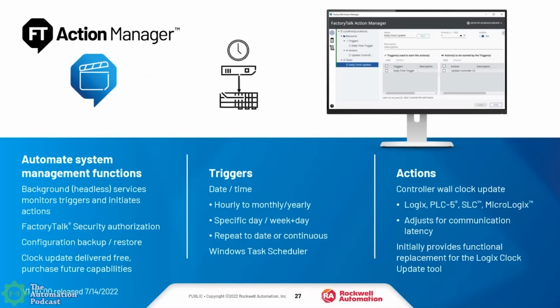So the device wall clock update is integrated into FactoryTalk Linx Network Browser and will support up to 1,000 controllers or actions. So this will even help with legacy PLCs, not just the most modern technology. It does go back all the way to PLC-5, as well as SLC and MicroLogix.